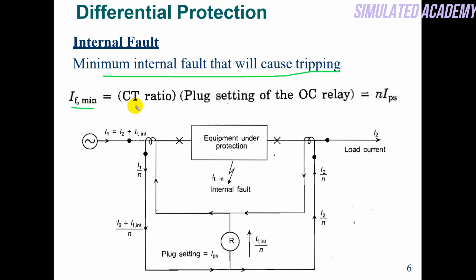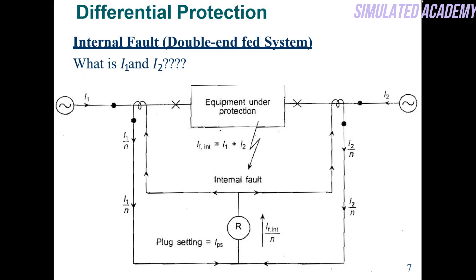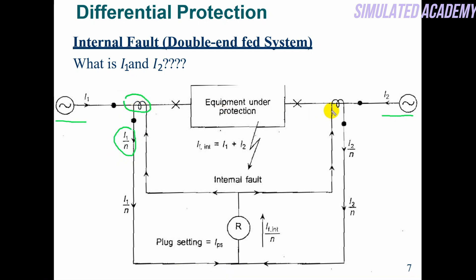How to deal with this fault — CT ratio and plug setting of the overcurrent relay. Plug setting is the value for which the relay must operate — the minimum value of current. Now if the system is fed from both sides and an internal fault occurs, i1/n from this CT and i2/n from that CT will flow, and all that current will pass through the spill coil because it is grounded. So the relay will operate again.